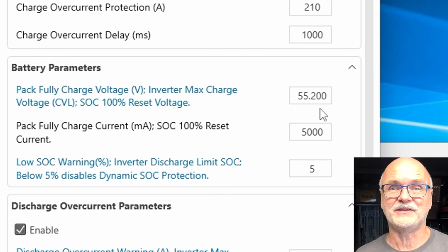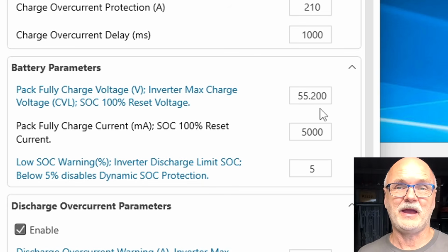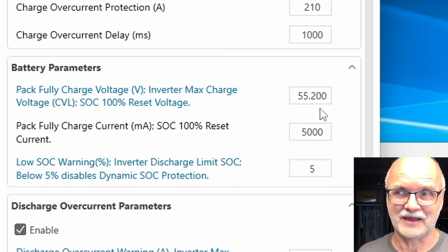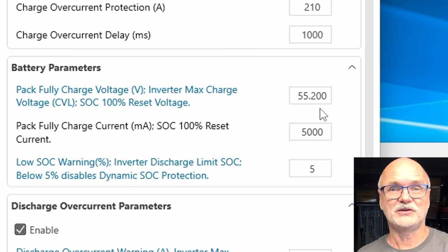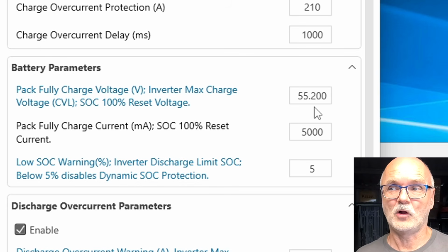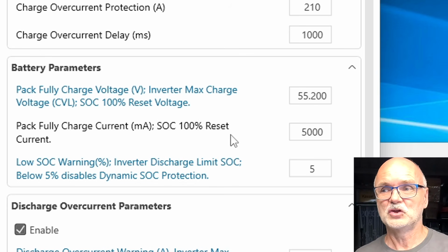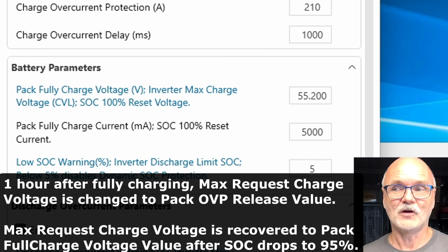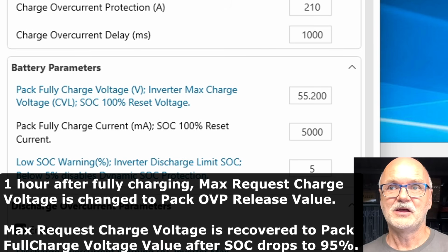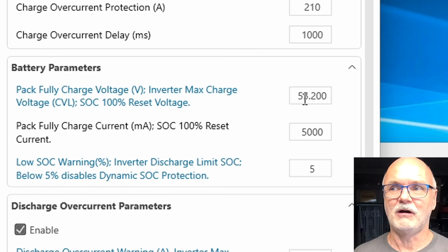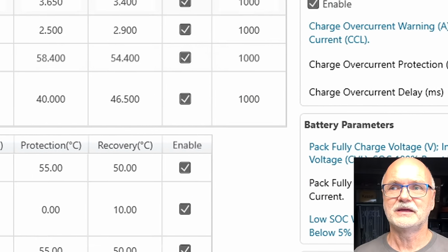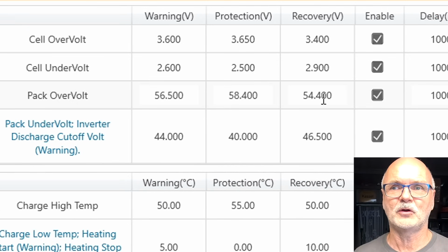This is for a very good reason, because fully absorbing the battery and balancing require this elevated voltage. So after 1 hour, this 55.2 volts will be lowered to the pack over voltage protection release value, going down to 54.4 volts.